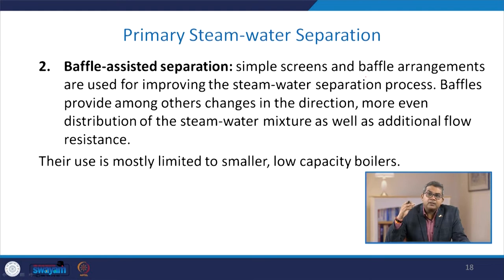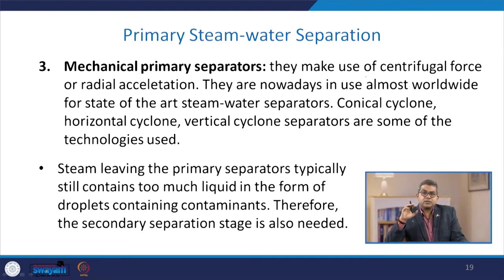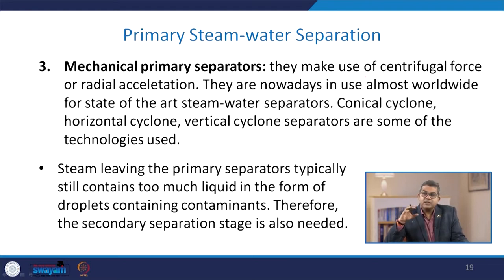Baffles provide, among other changes, changes in direction, more even distribution of the steam-water mixture, and additional flow resistance. Their use is mostly limited to smaller, low-capacity boilers. Third are mechanical primary separators, which make use of centrifugal force or radial acceleration — nowadays used almost worldwide for state-of-the-art steam-water separators. Conical cyclone, horizontal cyclone, and vertical cyclone separators are among the technologies used for this purpose.